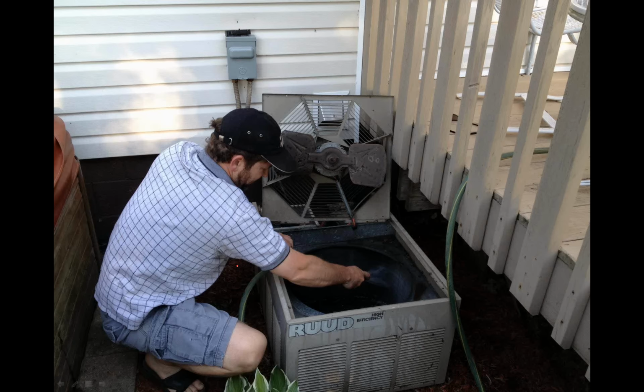So when you go to hook up gauges to a system, the very first things you've got to make sure of before you try to evaluate anything with charge at all are: is the condenser clean? Is the evaporator clean? Is the airflow correct? Because if those things aren't done first, you're wasting your time. You cannot get the charge correct on any system without cleanliness and correct airflow. It's absolutely impossible, and there's no use connecting gauges to a system before we do that.